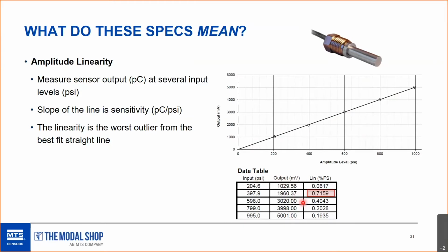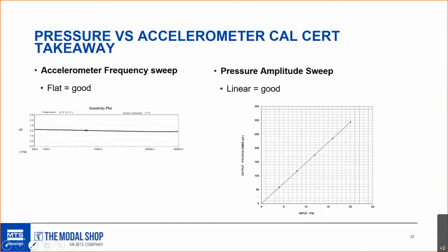And then for all that data, we draw a best fit straight line through all of it, and we measure the outlier data point, which is highlighted here in red. That's the worst case nonlinearity of the sensor, in this case 0.71%. We use that to compare against the spec sheet, which is typically 1%. It could be more, a 1 to 2% nonlinearity allowance. Those are the two main criteria for a pressure sensor calibration.